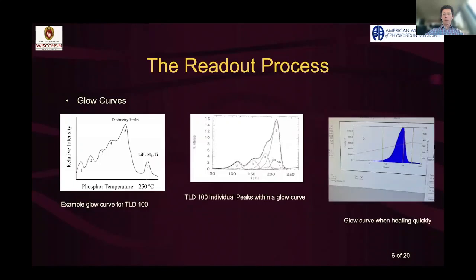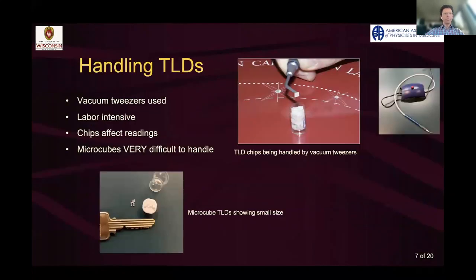But in reality, we typically like to heat them up a little faster. This is a glow curve from a 5500 reader, one of the automated readers, where the red line shows the increase in temperature or heat versus time. And then the big blue area is the area under the curve. And you can see you can't even distinguish the peaks on this glow curve, but that's okay because it's the total integrated area under the curve that's used for the TLD reading.